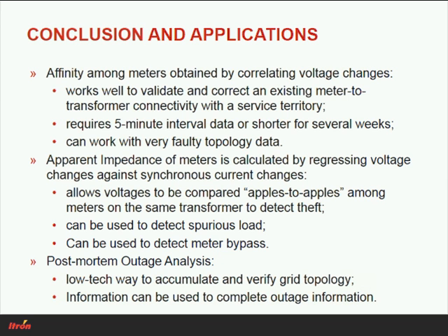We of course keep track of the margin of error of the impedances and also the R² of the correlation. And if it gets too bad, not all service drops will have a consistent measurement of impedance. For example, if somebody is absent a lot, it's very difficult to get an impedance with this method because there's very little load change. But again, a typical range is between about 20 and 100 milliohms that we found.